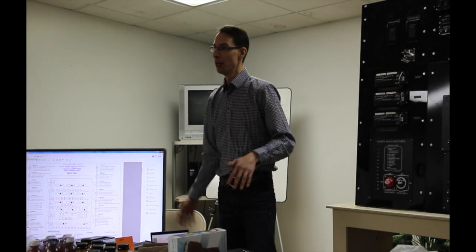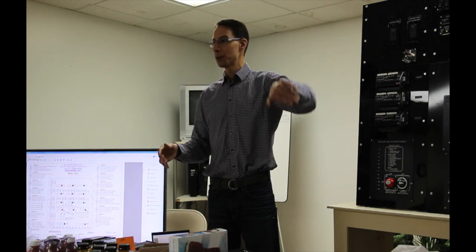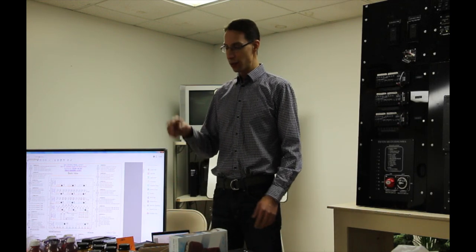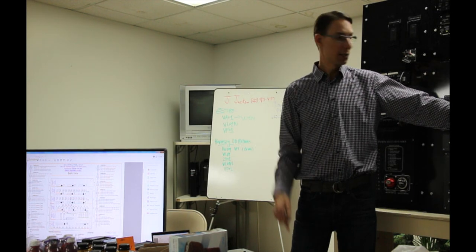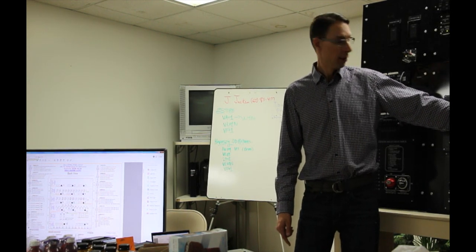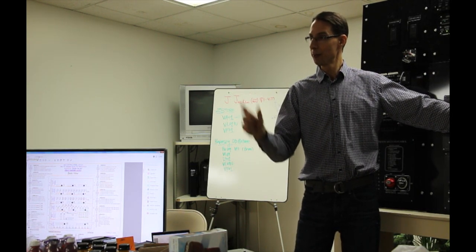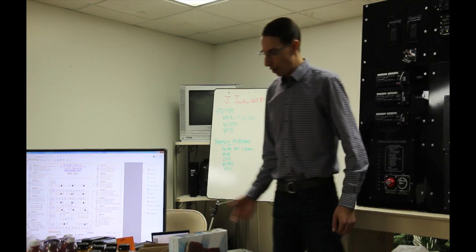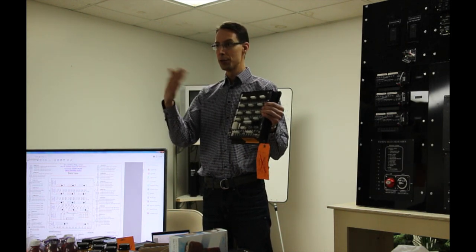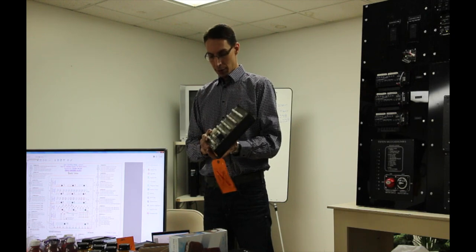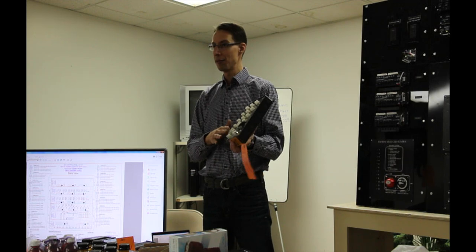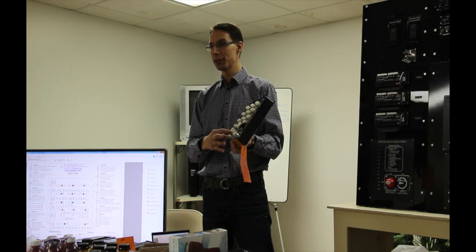So let's use that as an example. So the bedroom light switch and the closet light switch, you walk into the rear closet and there's a little push button rocker switch there. You push that switch and what it's doing is sending a ground signal to our connector on this panel. And it's literally like you pressing a button on the keypad. Every time you press that button it sends a ground signal and it's literally just like doing that. Sometimes, depending on the floor plan, a little rocker switch just inside the bedroom off by itself, that's exactly what it's doing there. So all we're doing is sending a ground signal to this input connector here so that we know when the user wants those lights turned on and off. So that's what these connectors do.